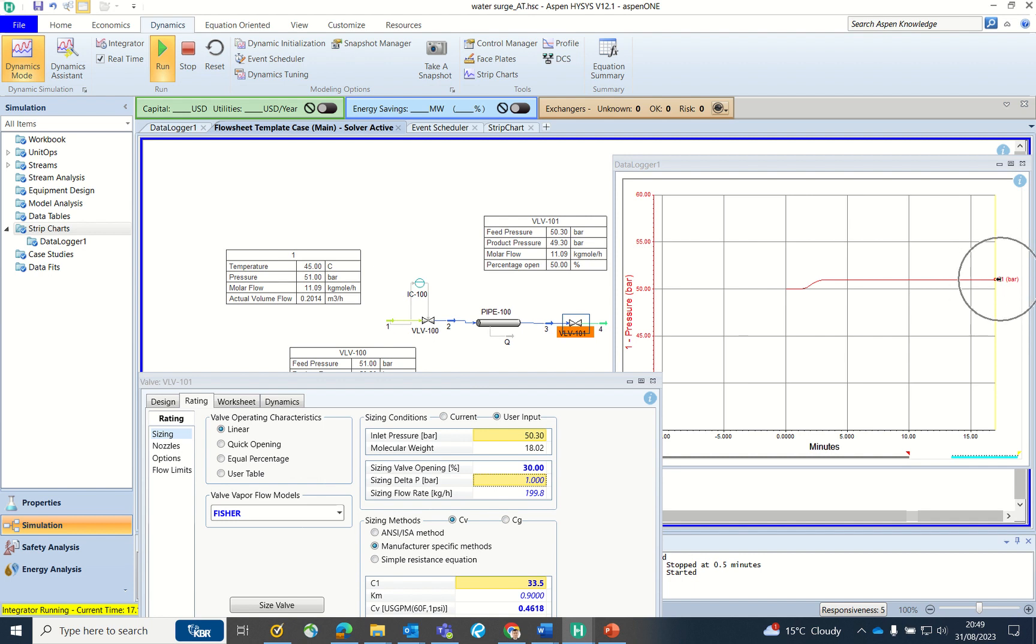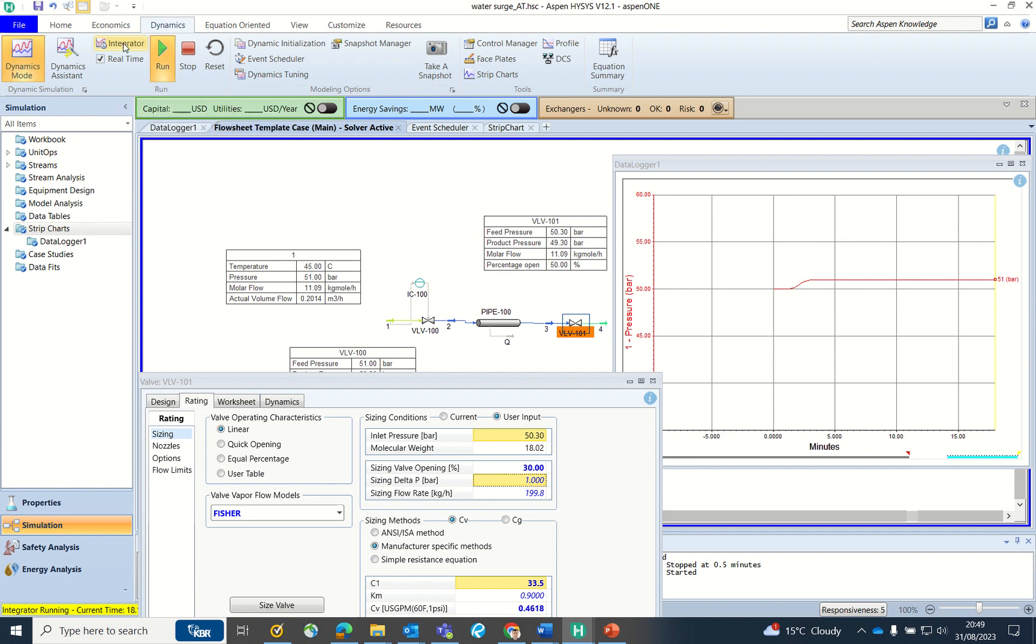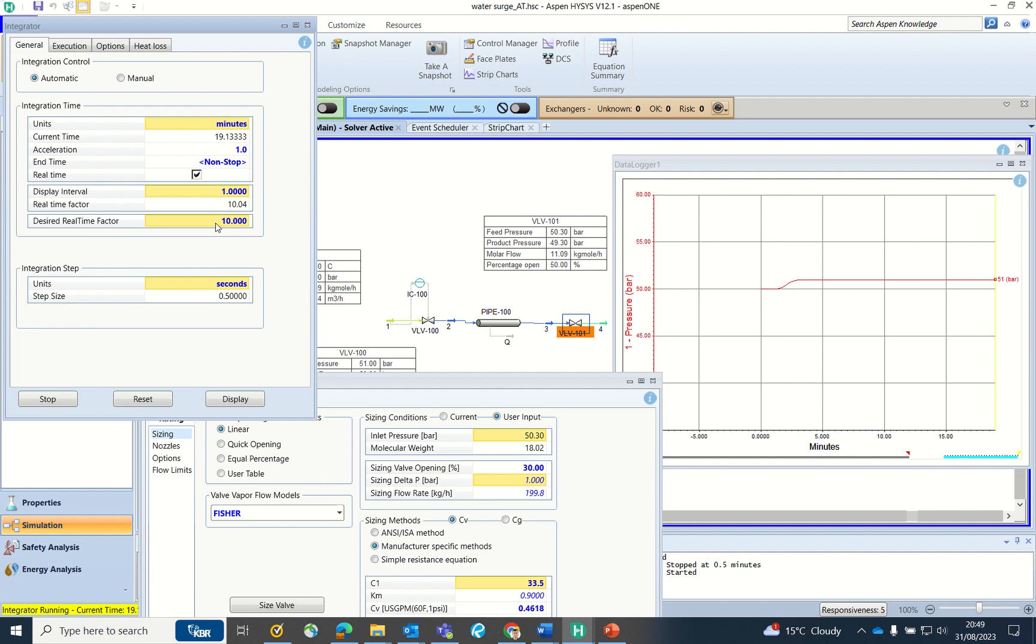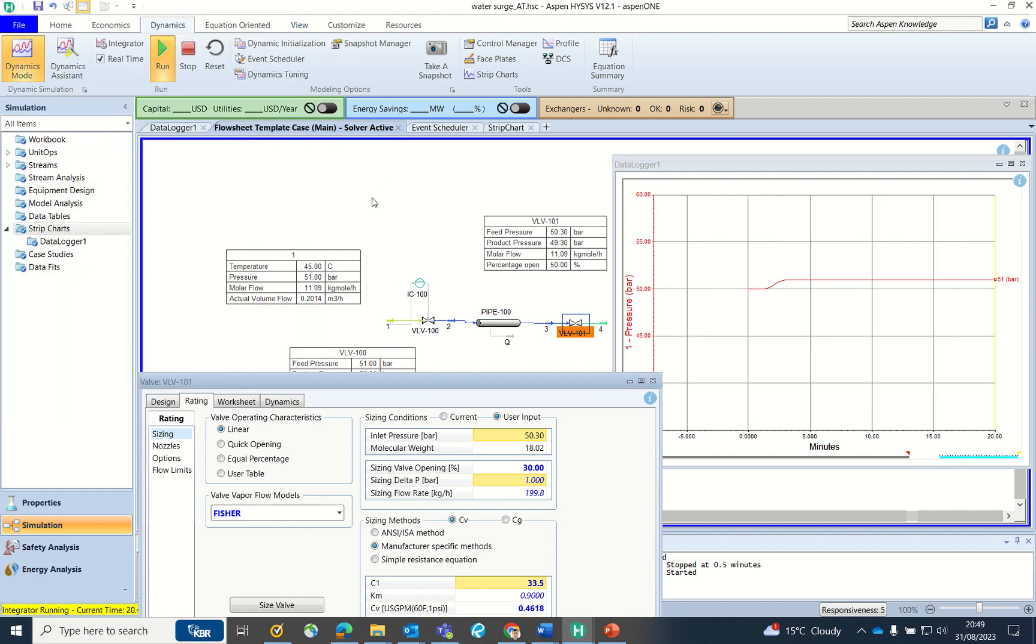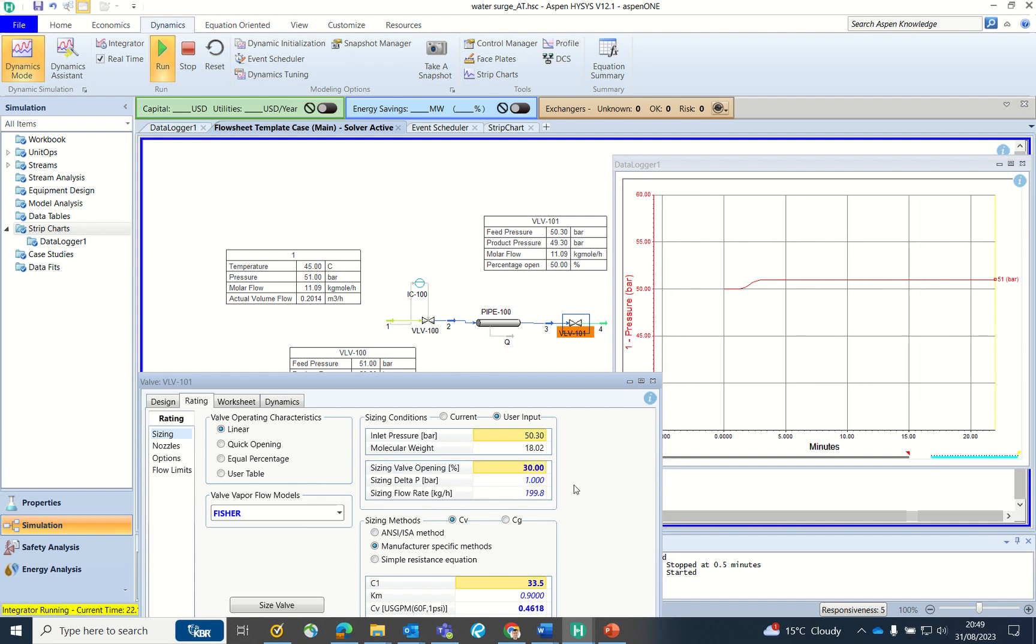Maybe not much, but you can see a slight increase in the pressure which might not have been picked here because this is just 10% closure of the valve. Let's make it 30% and wait for the chart to show some disturbances. Maybe I will increase the factor a bit but let's keep it running like this.